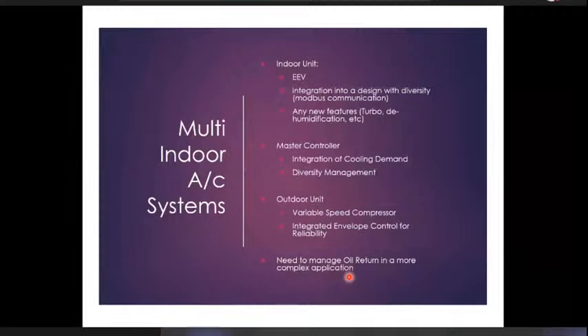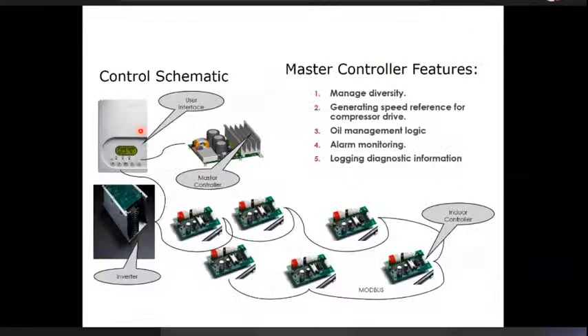This is typically a chain where there is a master controller with a user interface, and this is the inverter which drives the compressor. So the user interface is connected to the master controller. And then we have all of these small individual indoor temperature controllers in a multiple indoor unit connected to a single outdoor unit. So the master controller needs to know what is the cooling demand from each of these indoor units, which will be measured by the set point to actual temperature variation. And then based on the combined demand from all these 6 units in this example, it needs to take a decision on what speed or what percentage capacity the compressor needs to be driven.